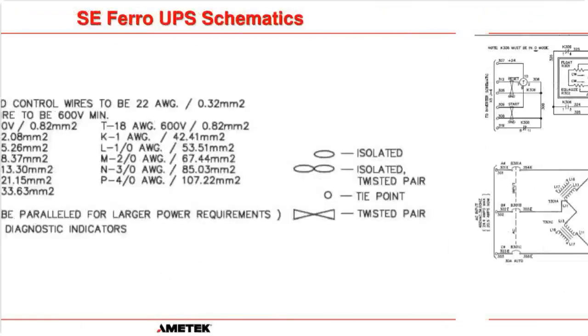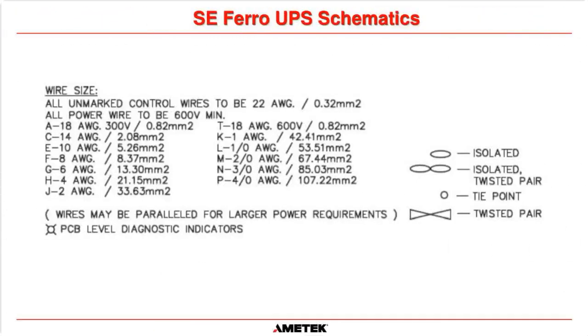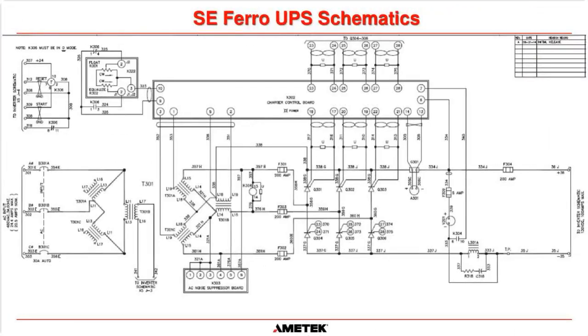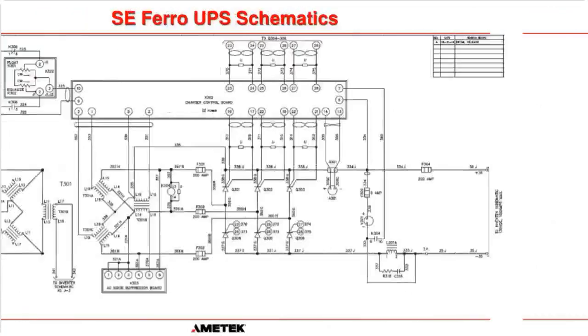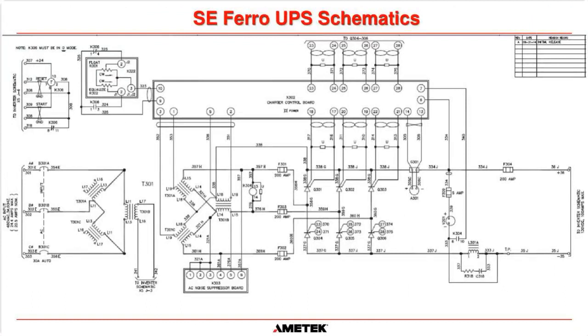So if we go back to our table, all unmarked cables will be 22 gauge. So if it doesn't have a letter after the wire number, then it is a 22 gauge cable. Okay. And that's listed on all of our drawings, so you can quite easily tell what size cable you're dealing with by looking at that. Oh, sorry, I went too fast. So let's go through the power flow of the system for the charger.